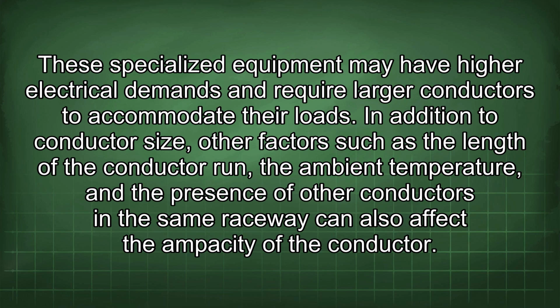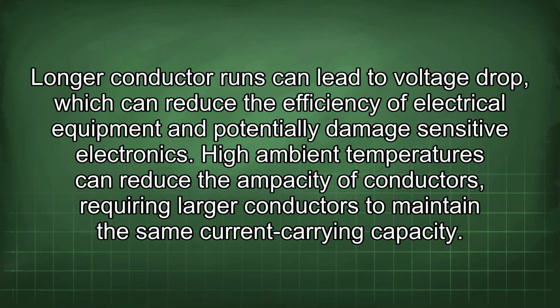In addition to conductor size, other factors such as the length of the conductor run, the ambient temperature, and the presence of other conductors in the same raceway can also affect the ampacity of the conductor. Longer conductor runs can lead to voltage drop, which can reduce the efficiency of electrical equipment and potentially damage sensitive electronics.